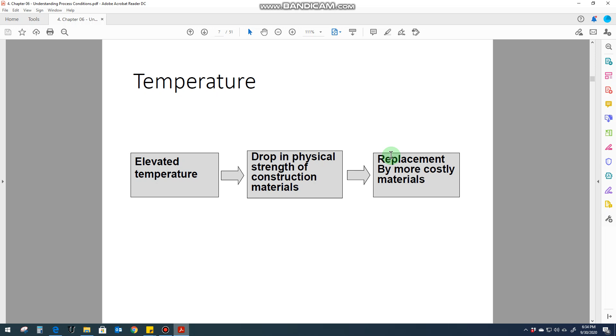Now here we have one example, and we will see how the temperature can affect the strength of the material. The maximum allowable tensile strength for a typical carbon steel and stainless steel at ambient temperature, 400 degrees centigrade and 550 degrees centigrade is provided below. So you can see here the temperature for the carbon steel, the grade is 70.